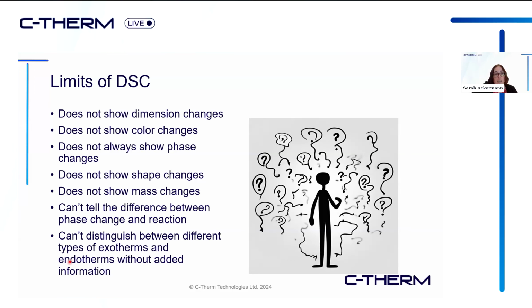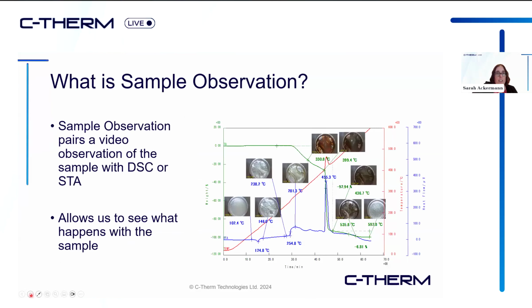So it's a very powerful technique, but except for a few special cases, it's not really a standalone technique. It's more of a technique that you use in partnership with other techniques. So sample observation pairs video, it couples video observation of the sample with either DSC or STA.